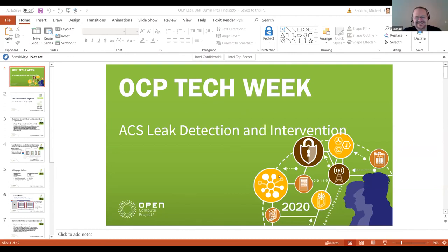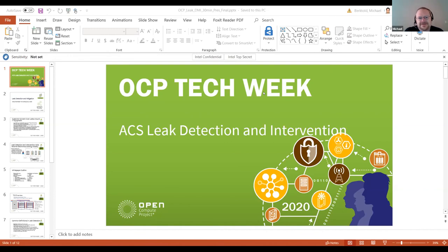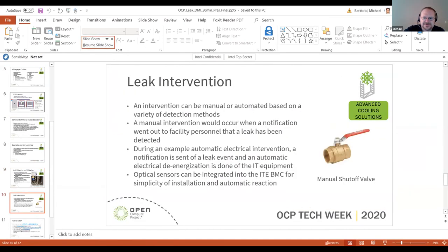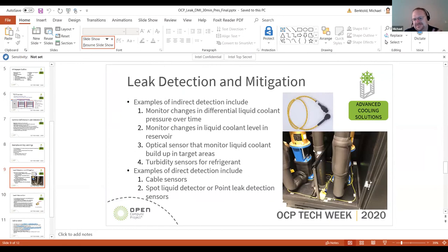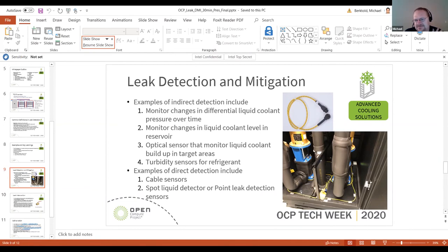Jason followed up: do you put any detection along those lines? Definitely — detection should be placed anywhere there's risk of a leak. In a CDU, route cable sensors around tubing. In a server system, route around cold plates and quick disconnect entry points. Basically, leak detection belongs wherever there might be a leak: a rope-style detector near interfaces, or a point detector in any reservoir underneath the system.